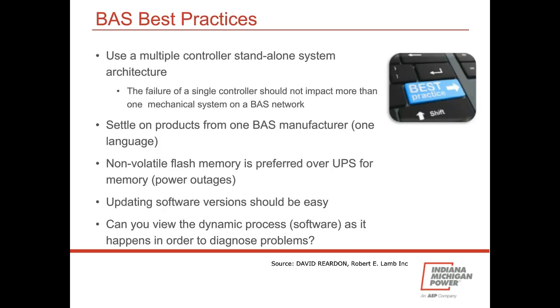A couple other tips here on overall building automation system best practices. You don't want a single point of failure, so it's best to consider using multiple controllers rather than a single controller, so that one going down won't impact more than one mechanical system or zone.